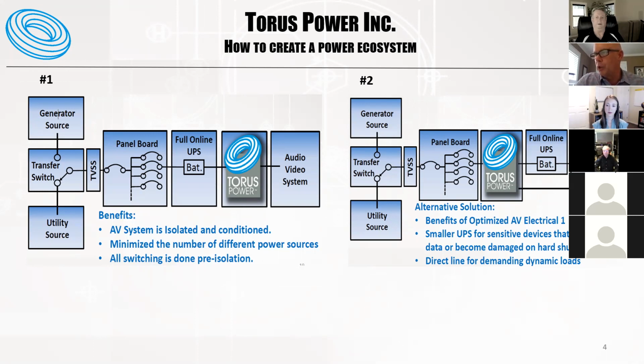And we're showing 2 pictures here for adding a UPS. The first is where you're adding a full online UPS that'll control and power the entire system behind the Torus Power unit. And the second is adding a UPS after the Torus Power unit, where you're just looking at some critical components like your network gear. So a couple different ways of wiring or setting up the system.